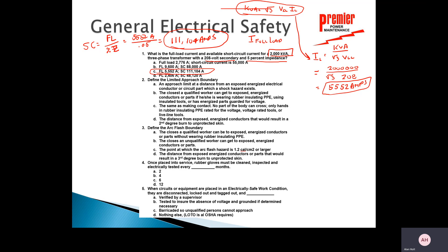Now some definitions from NFPA 70E. Define the limited approach boundary. One possible answer is: an approach limit at a distance from an exposed energized electrical conductor or circuit part at which a shock hazard exists. Another option described the closest a qualified worker can get using rubber insulated gloves and PPE — but that would be the restricted approach boundary. The answer is: it's the approach limit distance where you must start being concerned about shock hazard analysis.